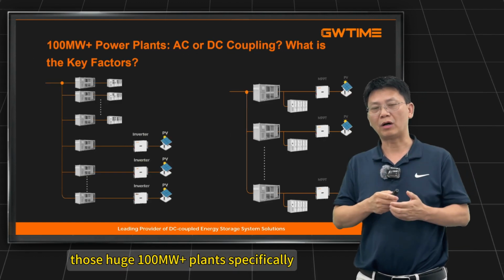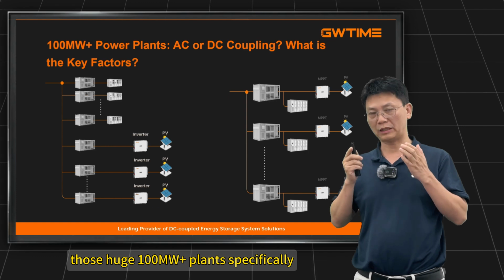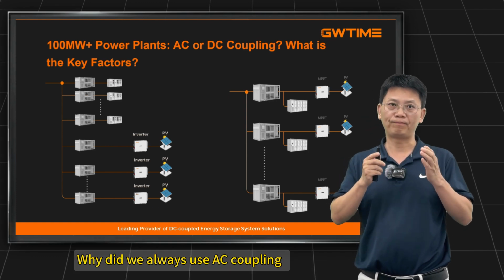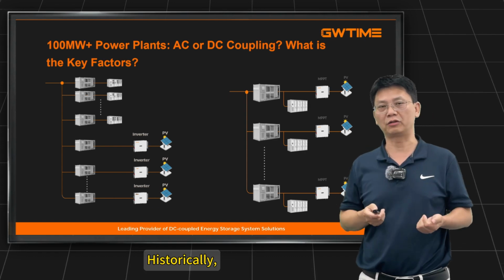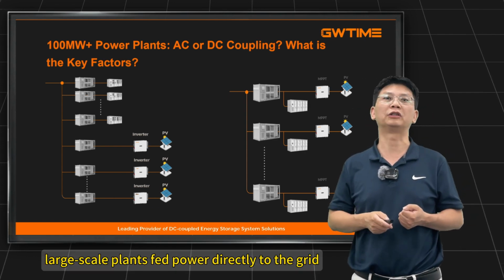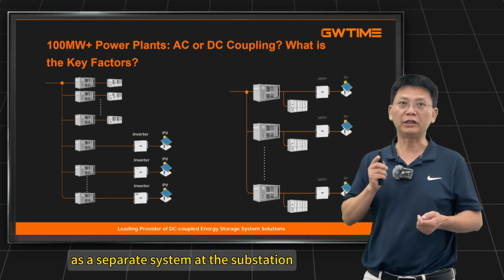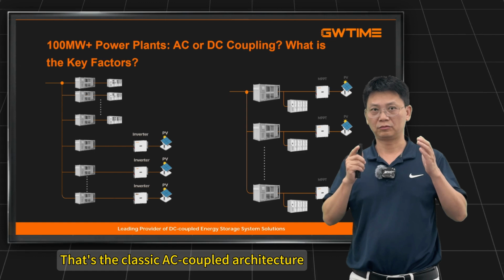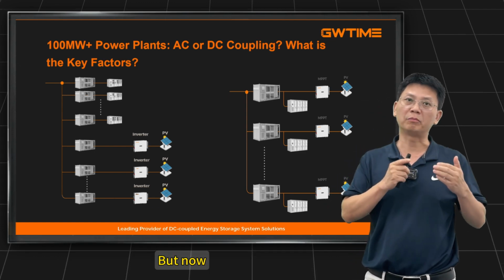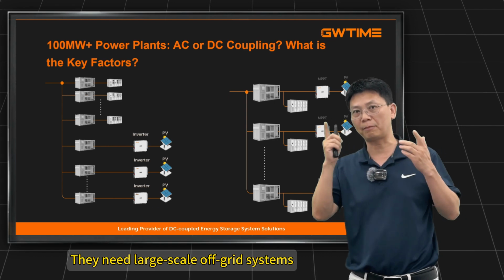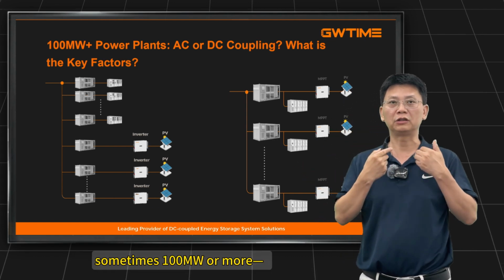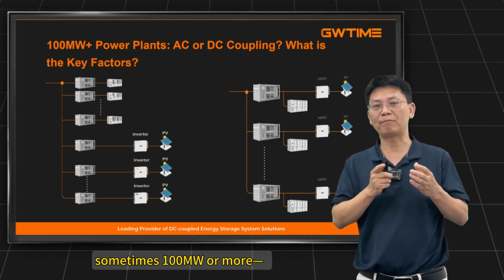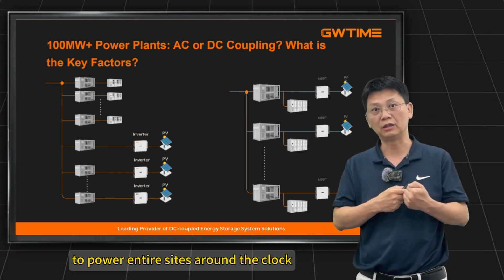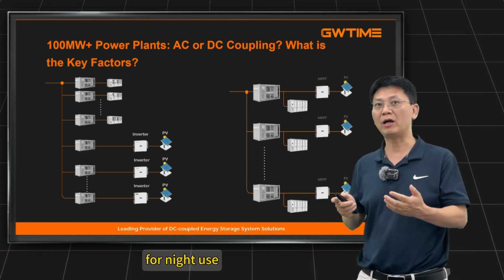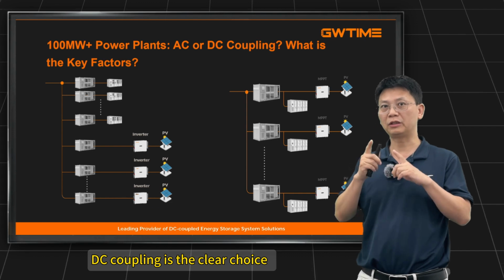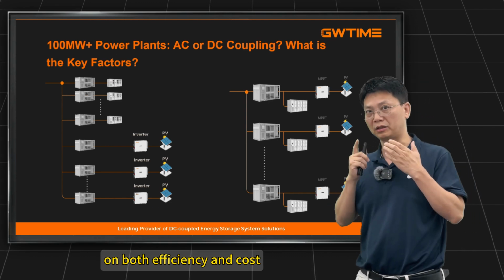Now, let's talk about those huge 100 megawatts plus plants specifically. Why did we always use AC coupling for these before? Historically, large-scale plants fed power directly to the grid, and storage was added later as a separate system at the substation. That's the classic AC coupled architecture. But now, look at overseas ports and mines. They need large-scale off-grid systems, sometimes 100 megawatts or more, to power entire sites around the clock. They need to save daytime solar for night use. For them, DC coupling is the clear choice on both efficiency and cost.